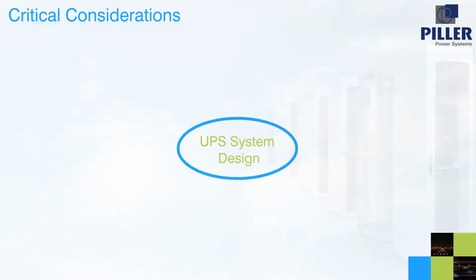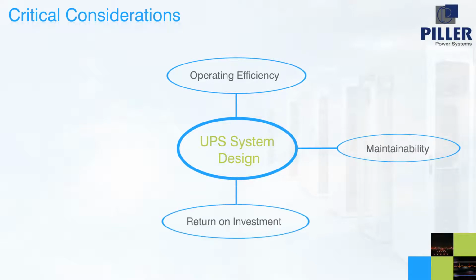The UPS system design has to maximize operating efficiency, maintainability, return on investment, and of course, reliability. With ever-increasing costs of energy, new solutions are required that can deliver high reliability without compromising data center economics. In exploring what is traditionally available, we can see that each different system configuration to introduce redundancy and so increase reliability has limitations.